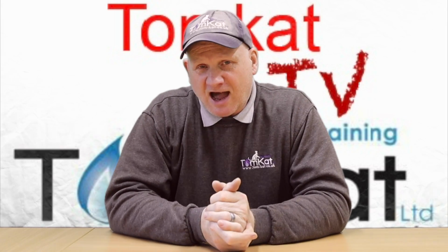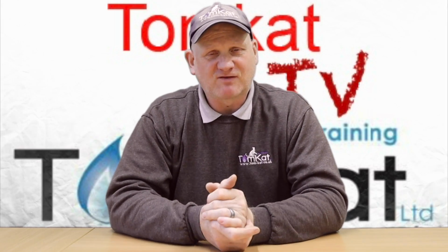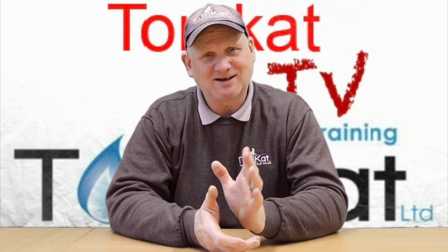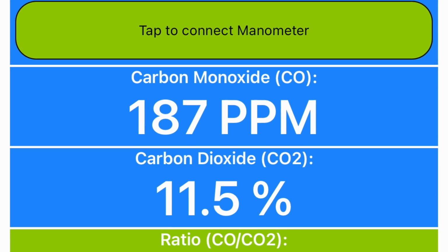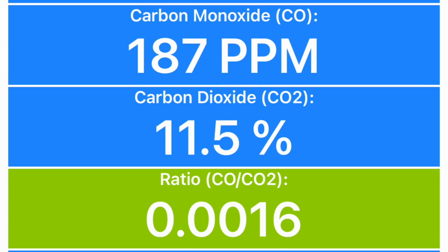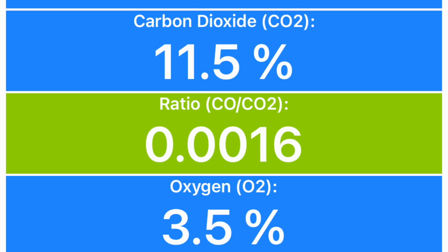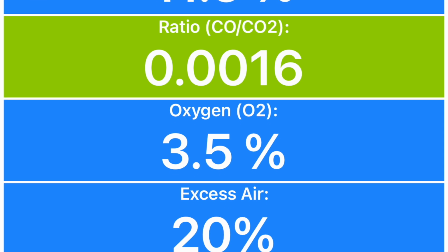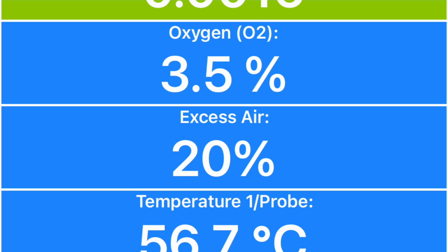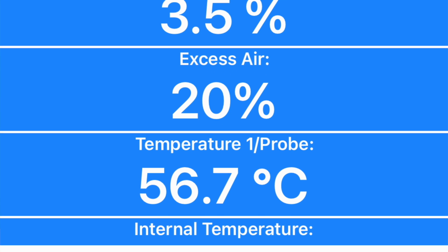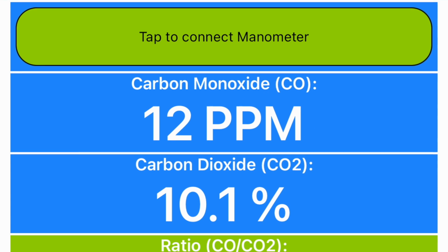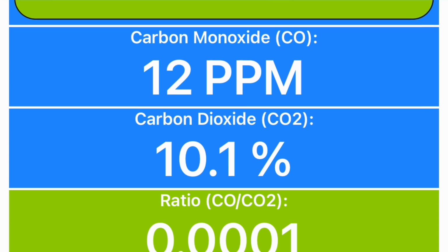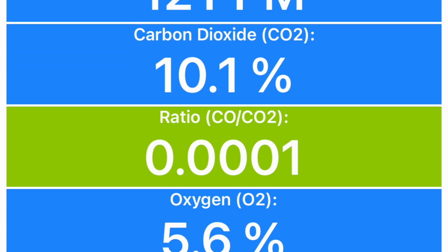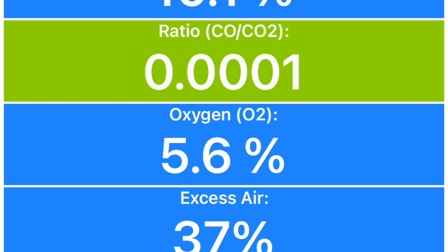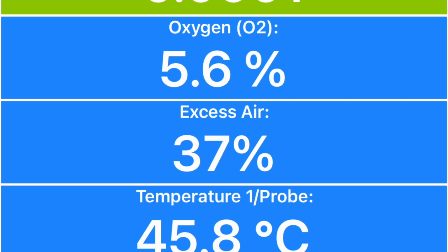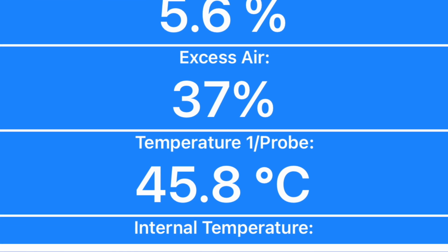So after about another half an hour of messing around with the settings on the gas valve, I managed to get it somewhere near. On the maximum setting, I got 187 parts per million of CO, I got 11.5% CO2, and I got a ratio of 0.0016 with a flue temperature of 56.7 degrees centigrade. On the low setting, I got 12 parts per million of CO, I got 10.1 CO2, I got a ratio of 0.0001 with a flue temperature of 45.8 degrees C.